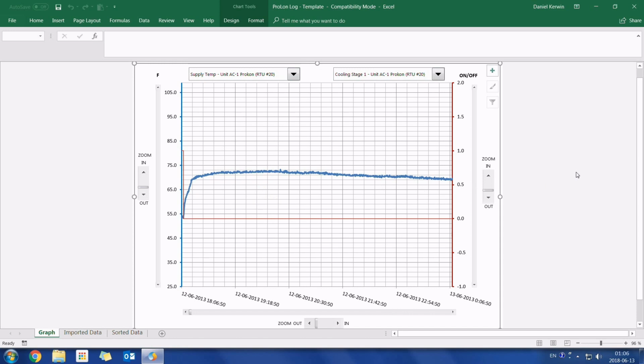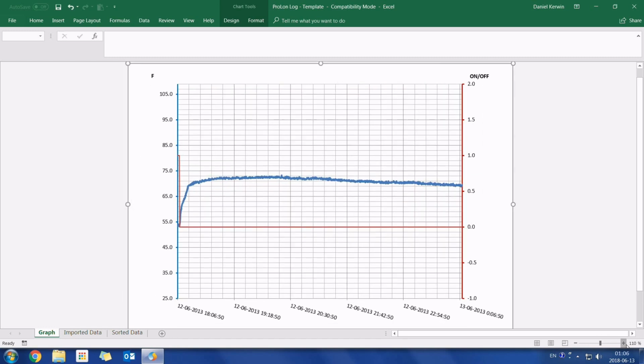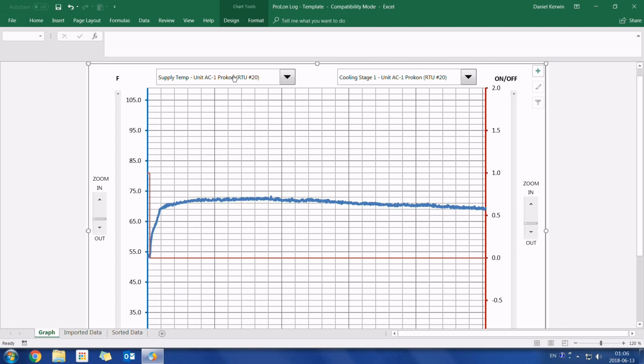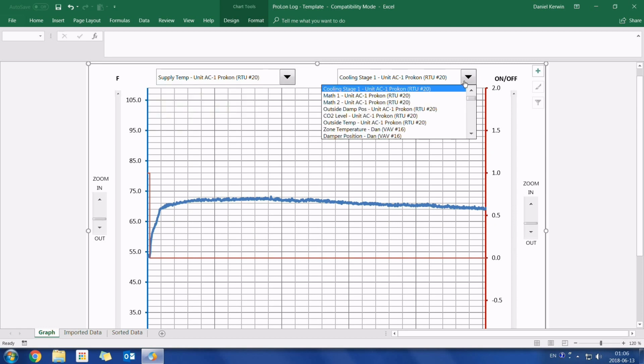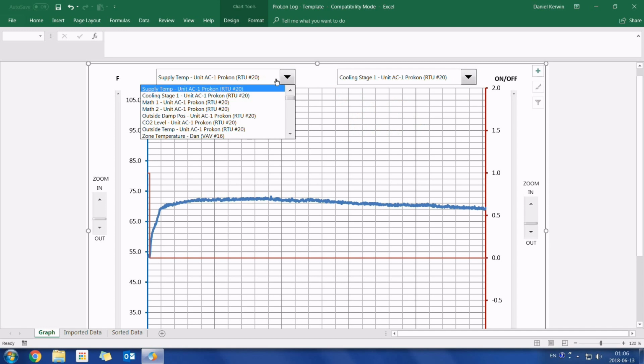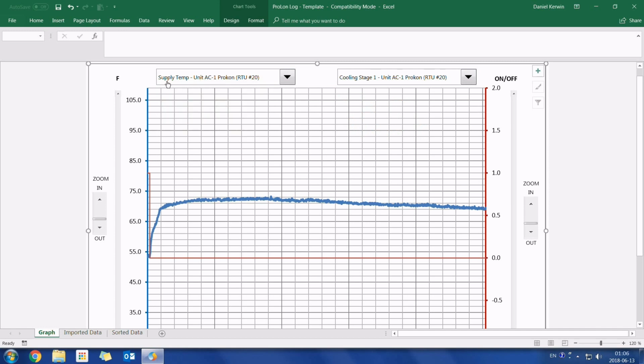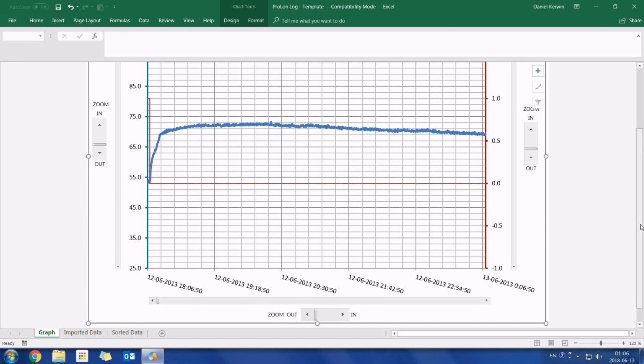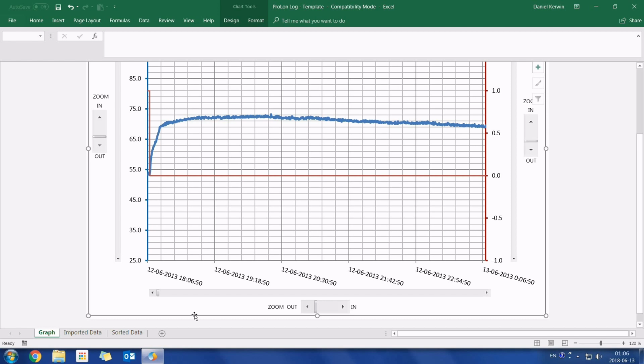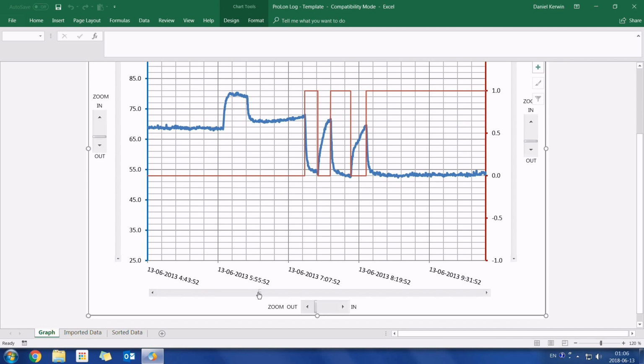And there we go. What this Excel file does is that once it opens the data log file, it's going to configure everything so that we can see it in a graph. I'm just going to zoom in a little bit here. So we can compare any two variables at the same time. In this case, I'm looking at the supply temperature and the cooling stage 1. I'm just going to move up in time here. So here we have our timestamp at the bottom, so we can move the time up. There we go.